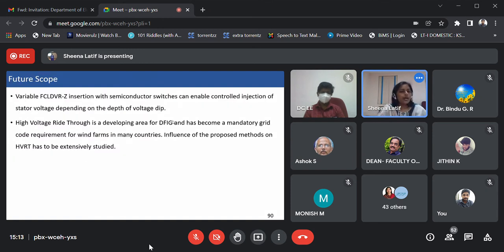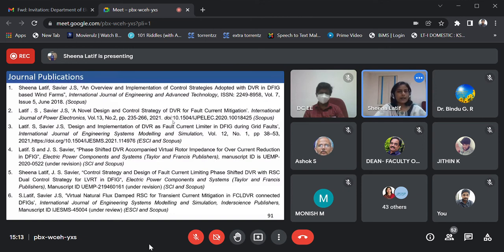As a future scope, the high voltage ride through or HVRT requirement is a developing area for DFIG and has also been made mandatory by some of the grid codes. So the influence of the proposed methods on the HVRT has to be extensively studied. And the variable FCL-DVR impedance insertion with semiconductor switches can also enable better control of the stator voltage as well as stator current. These are the publications.